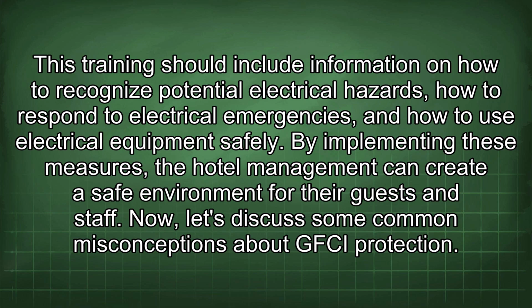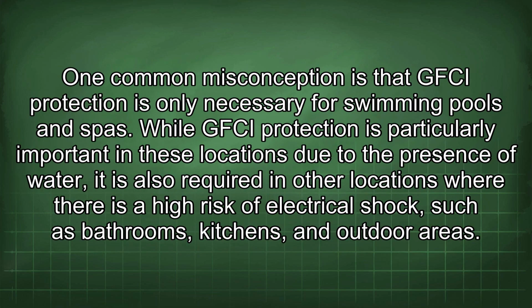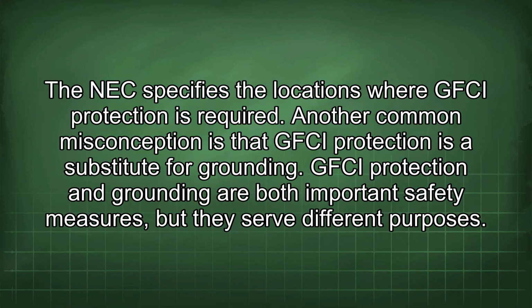Now, let's discuss some common misconceptions about GFCI protection. One common misconception is that GFCI protection is only necessary for swimming pools and spas. While GFCI protection is particularly important in these locations due to the presence of water, it is also required in other locations where there is a high risk of electrical shock, such as bathrooms, kitchens, and outdoor areas. The NEC specifies the locations where GFCI protection is required.